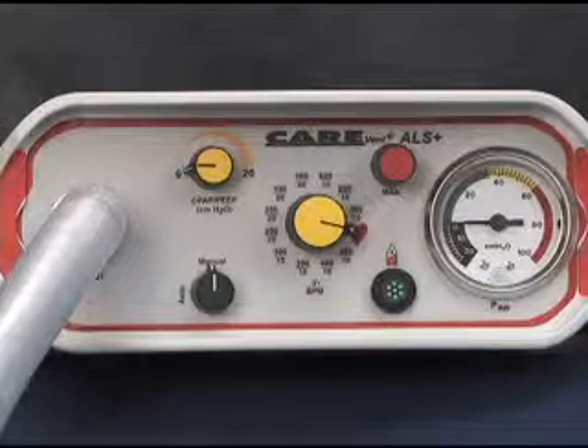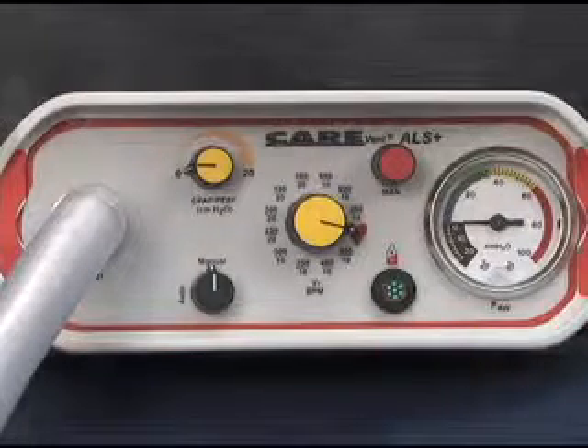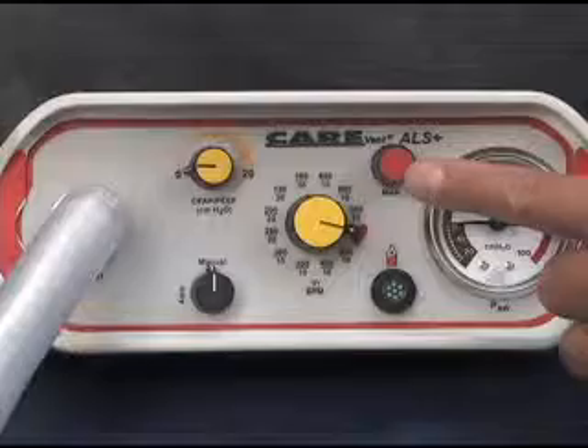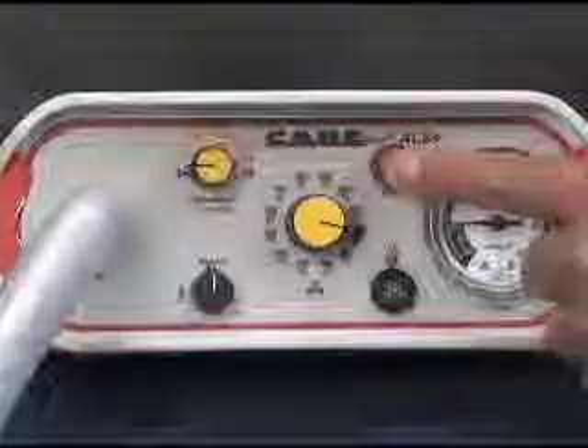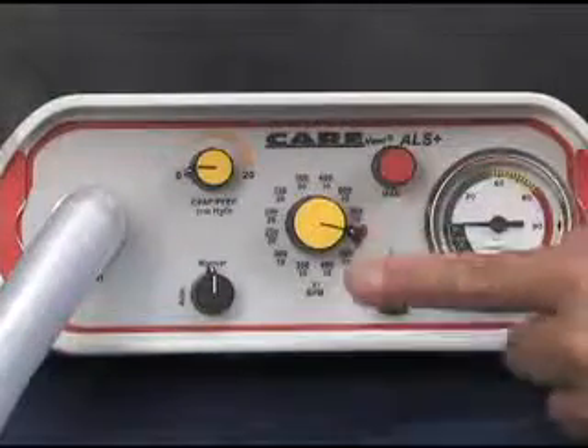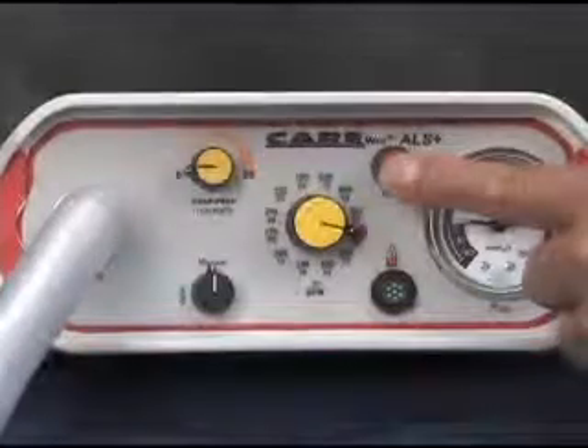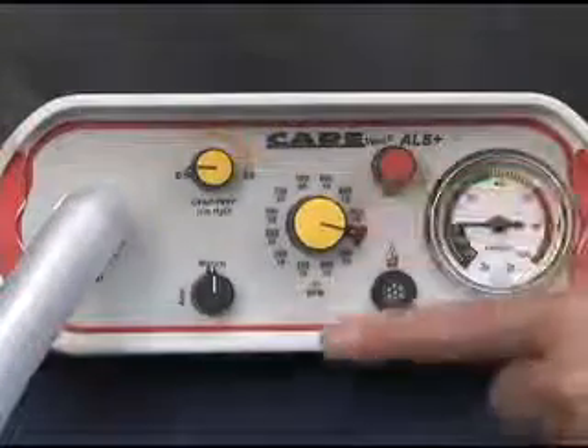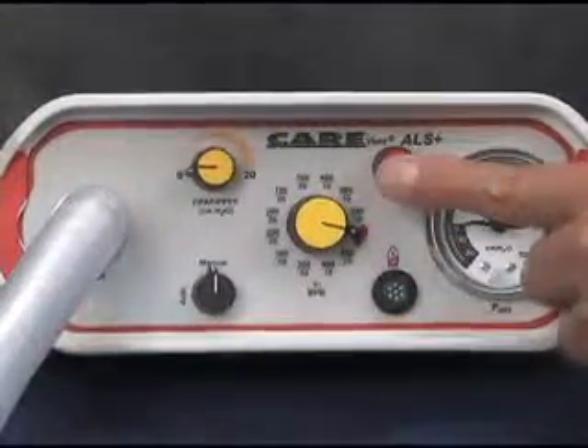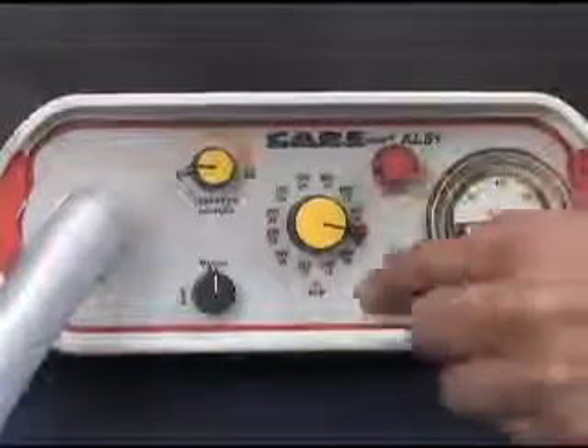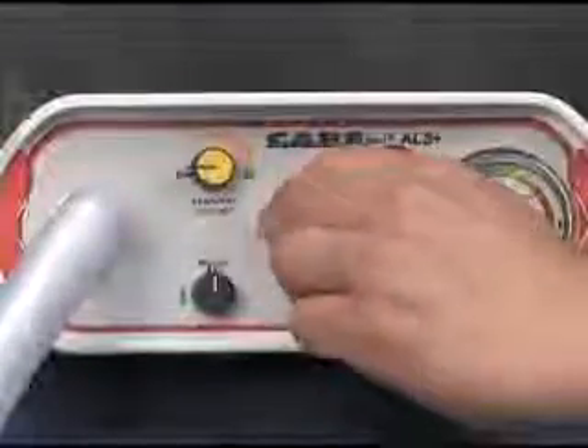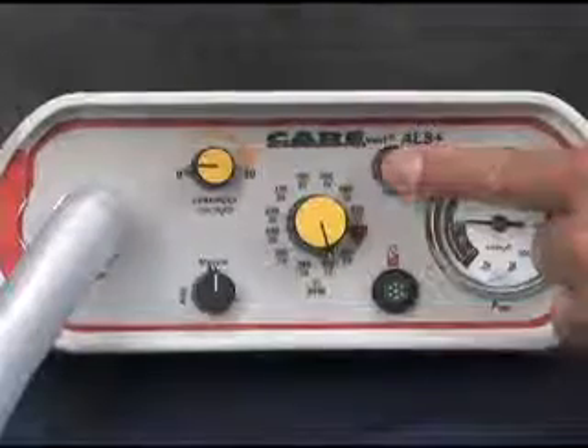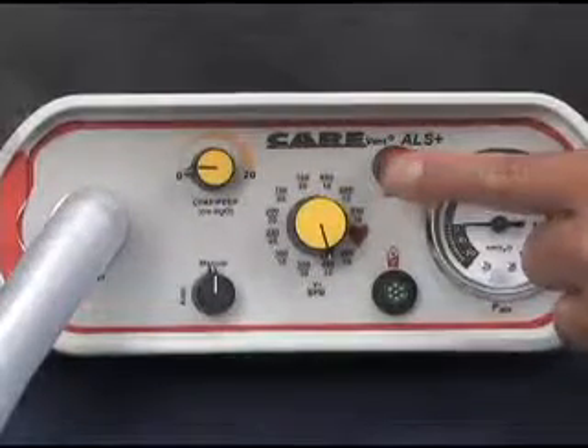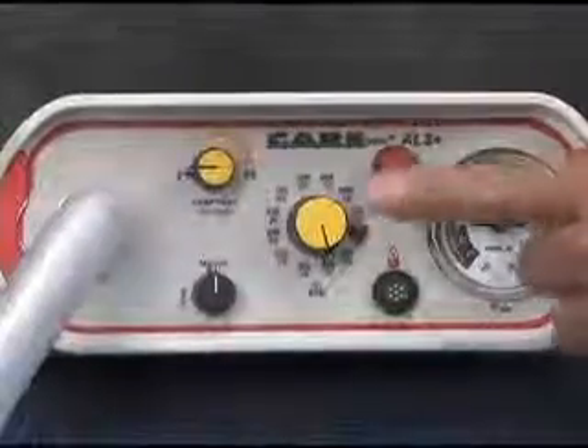The manual position will allow the operator to provide manual ventilations using the manual override button. These manually actuated ventilations can be used to support a patient in respiratory distress, or to provide manually triggered ventilations to a non-breathing patient. The flow rate provided by the actuation of the manual button is equivalent to the pre-selected automatic setting on the rotary setting selector control.